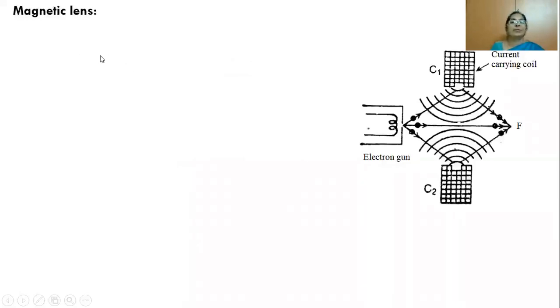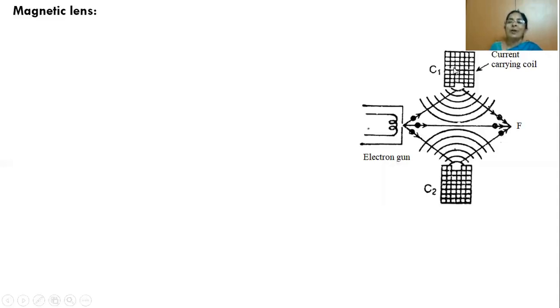Next, let us see how a magnetic field works as a lens. A coil carrying current is enclosed in an iron cylinder with a hole. Another coil carrying current is enclosed in another iron cylinder, also with a hole. When current flows through the coil, it produces a magnetic field. Iron, being magnetic, holds the magnetic flux lines. One coil with current in one direction forms the north pole, and the other with current in the opposite direction forms the south pole.